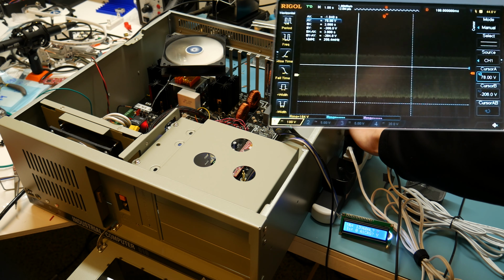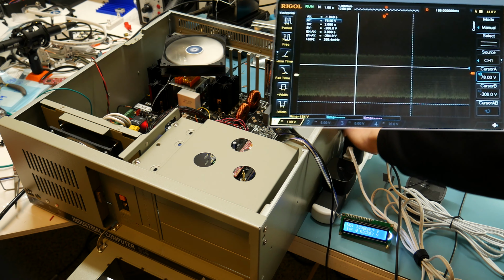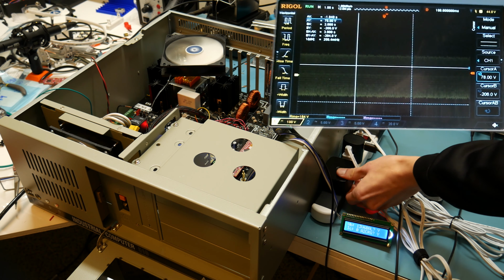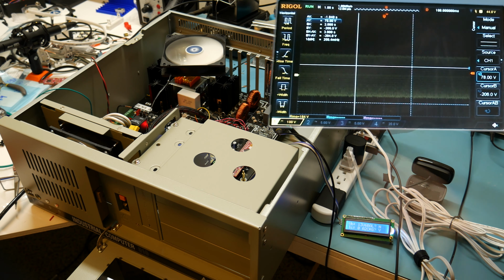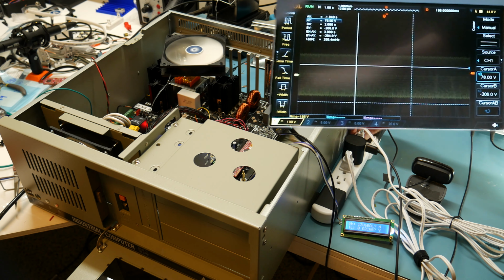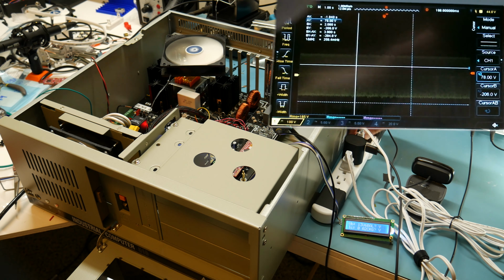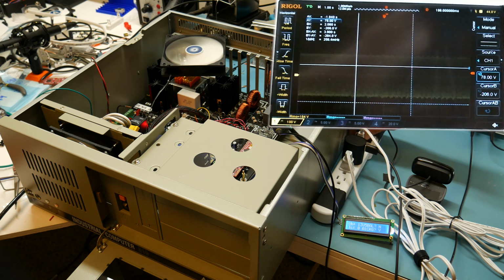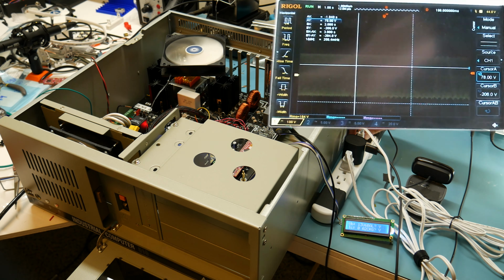Ironically, the best way for me to trip this hiccup overcurrent mode routine is using inrush current, which is the thing that our soft start is meant to prevent. I'm going to try and hot plug some devices into our power strip that we've plugged into the UPS and see if we can get that hiccup mode overcurrent protection to activate.